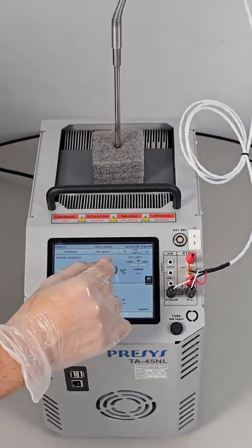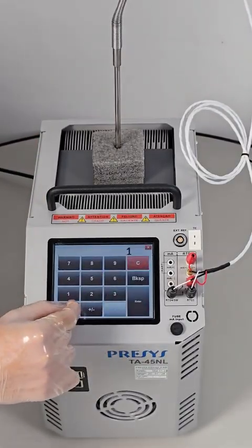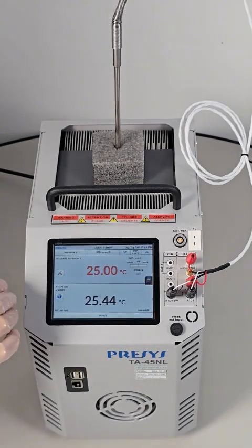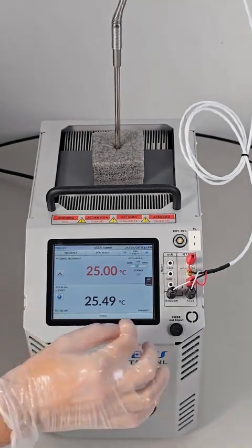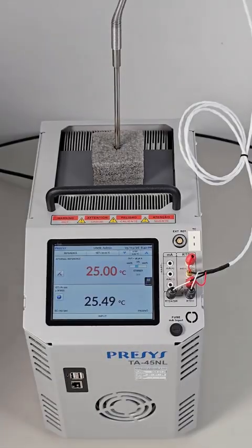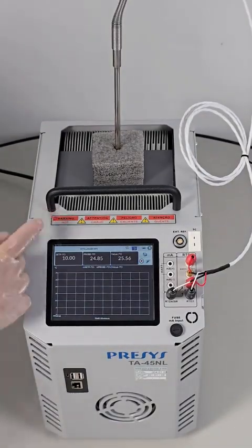Set the TA-45NL set point to 10 degrees Celsius to promote thermal equalization of the entire system. The exact value is not critical. It serves as an intermediate preparation temperature.